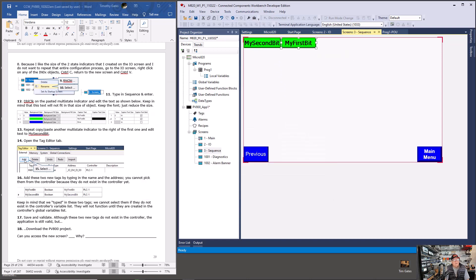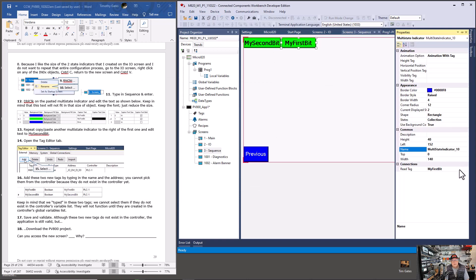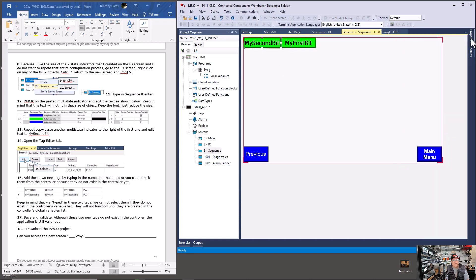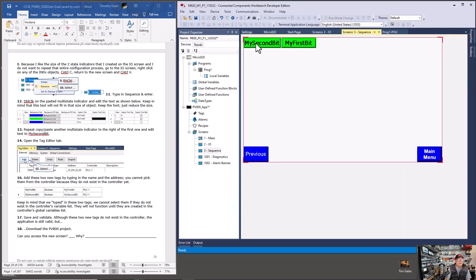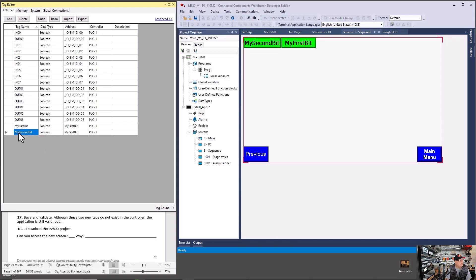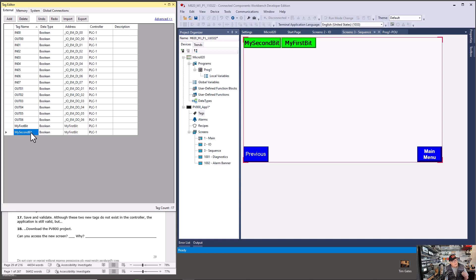Then, of course, you had to go to properties, go to the read tag, and pick my first bit. And then the same thing for my second bit. And I see that I didn't change that one yet. So I'll do that now. Now the text is changed and the read memory location is changed. I also pointed out if you had to go to tag and make sure that you had those two tags already in the tag database for your HMI. Because remember, the tag database for the HMI is not the same as the tag database in the PLC. This is the tag name in the HMI. These are the memory locations in PLC1.